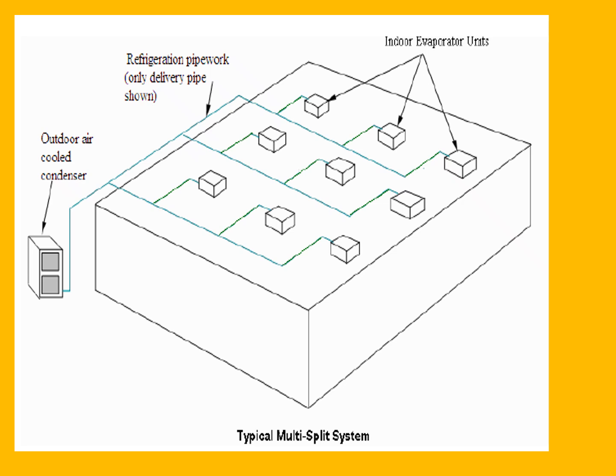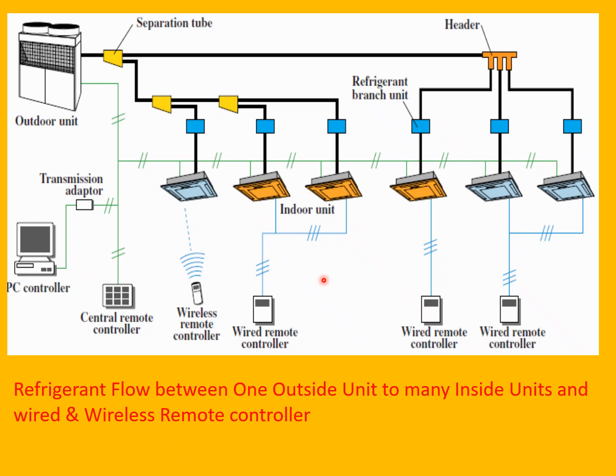Friends, this diagram shows you a typical multi-split system of VRF, in which the outside unit is one and it is supplying refrigerant to a number of inside units. Here 9 different units are shown. This particular diagram shows refrigerant flow between one outside unit and many inside units. These are inside units. This is the outside unit. All these inside units are cassette type, but they may be floor mounted or wall mounted type also.